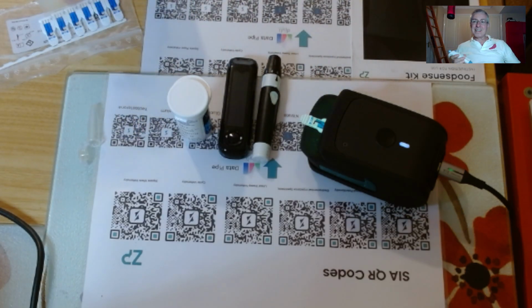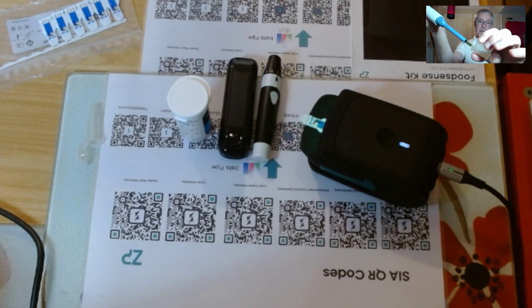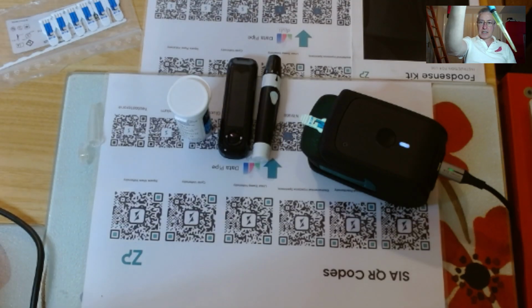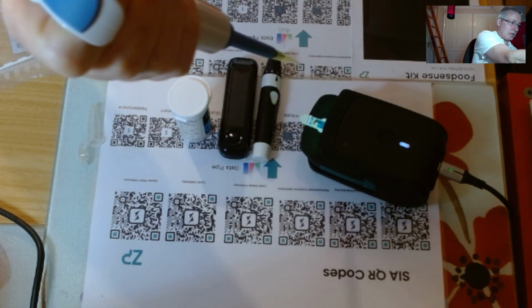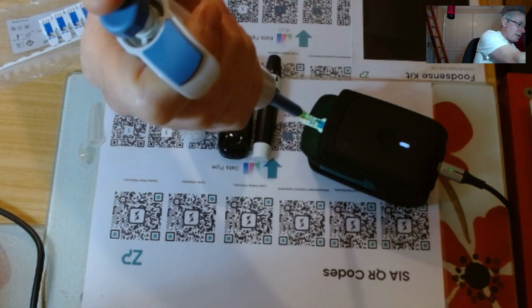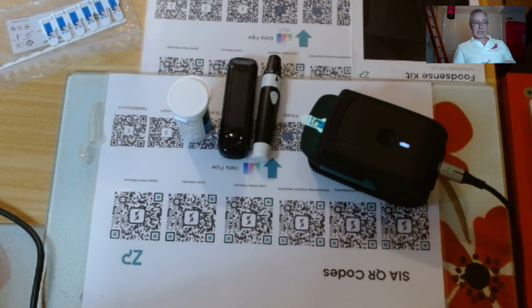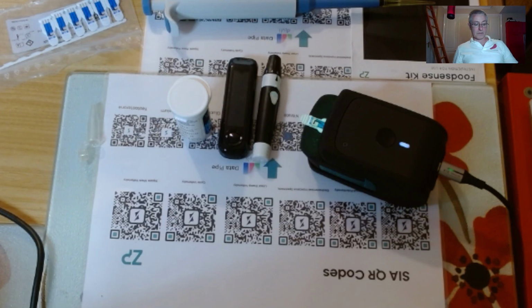The reason I say this is really important is that even if something is hot, 50 microliters is a tiny amount of liquid. By the time I've taken this sample, moved it over to here, and put it on there, that's a tiny volume. That volume is not going to hold on to temperature. So if it's coming out at 70 degrees C or 50 degrees C, it's going to cool very quickly. The quick answer to your question is the sample should really be at 20 to 28 degrees Celsius. A sample that size in an environment that's, say, 25 degrees C, is very quickly going to get to 25 degrees Celsius.